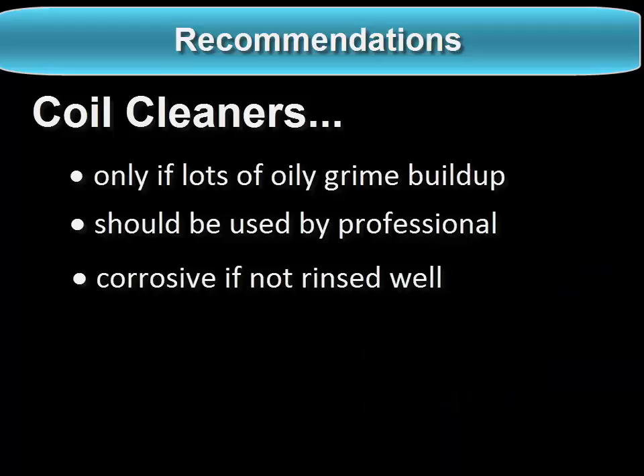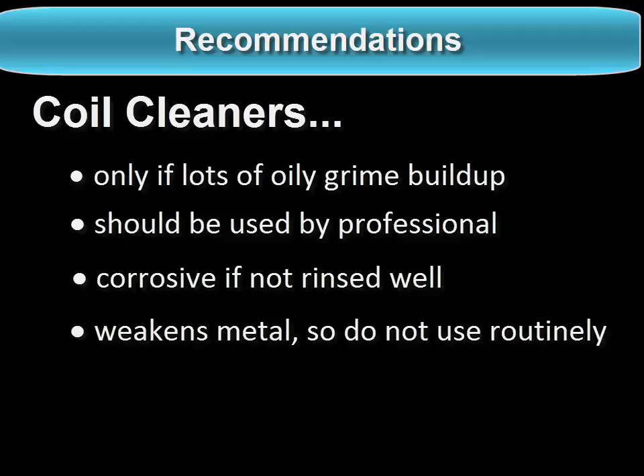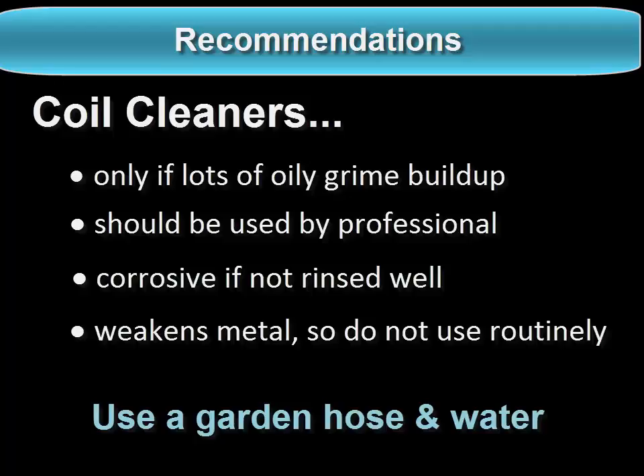Coil cleaners are tough chemicals that can not only burn holes in your clothes, which is why you must wear protective equipment, but can damage paint too. Consistent use of these cleaners over time can dissolve the outer metal and can diminish the life of the coil, so we do not recommend using them for routine maintenance. We recommend using just a garden hose and water.